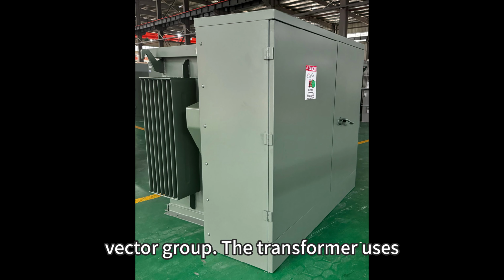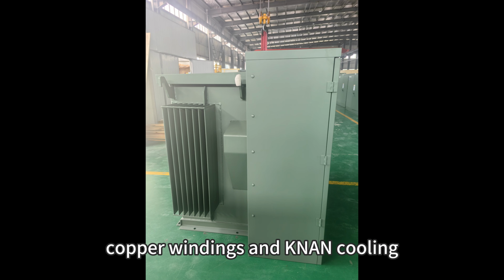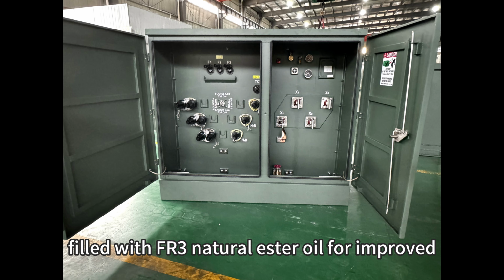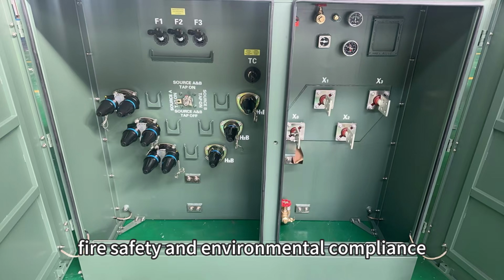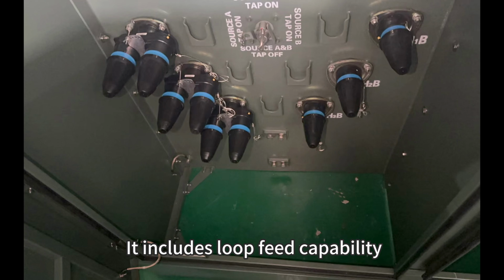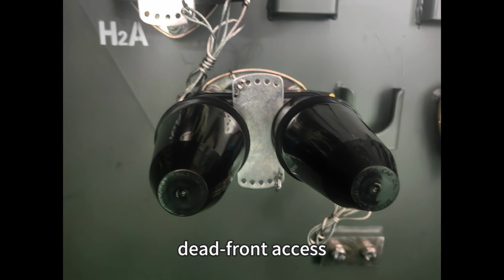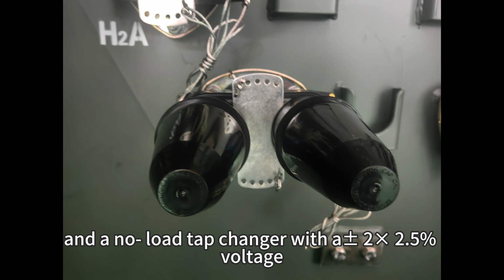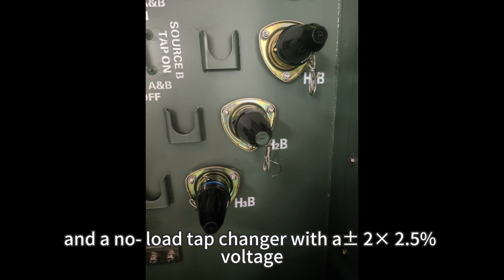The transformer uses copper windings and ONAN cooling, filled with FR3 natural ester oil for improved fire safety and environmental compliance. It includes loop feed capability, dead front access, and a no-load tap changer with a ±2 x 2.5% voltage adjustment range.